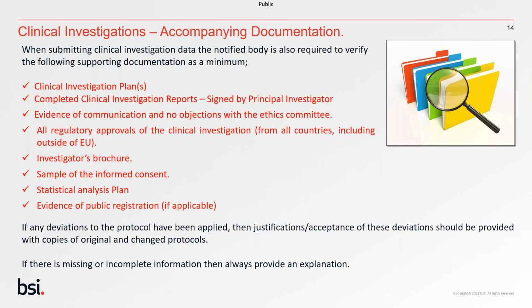I think it's Annex E of ISO 14155 in particular that talks about a huge list of documents that are required to be considered as part of a clinical investigation. Sometimes it's just good to let us know if there's anything in there that actually hasn't been collected, and a justification as to why you chose not to use that particular documentation, or why there is an exemption, for example.